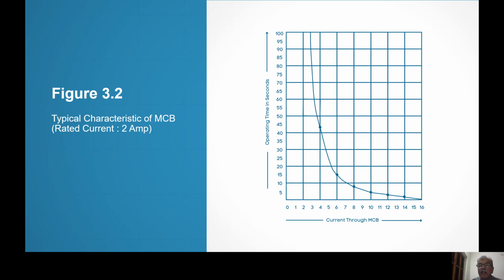And therefore, my MCB characteristic, that is, the tripping characteristic, should be below the thermal withstand curve of the equipment to be protected. The thermal withstand curve of the motor to be protected. That one has to remember, and that is how one has to engineer.